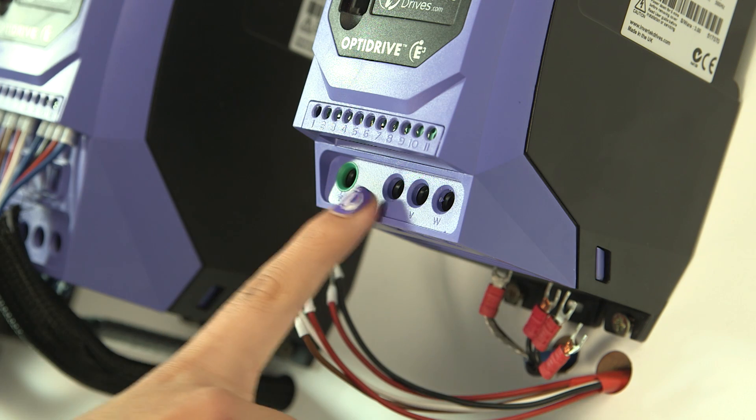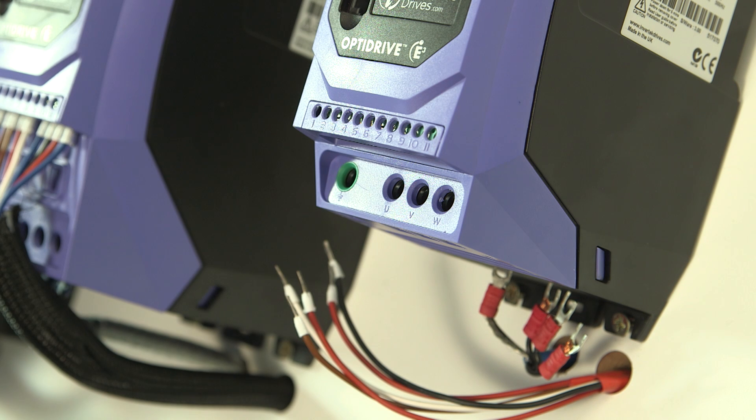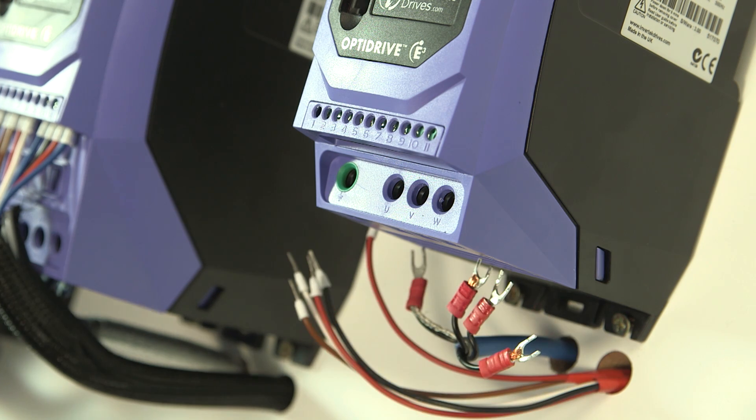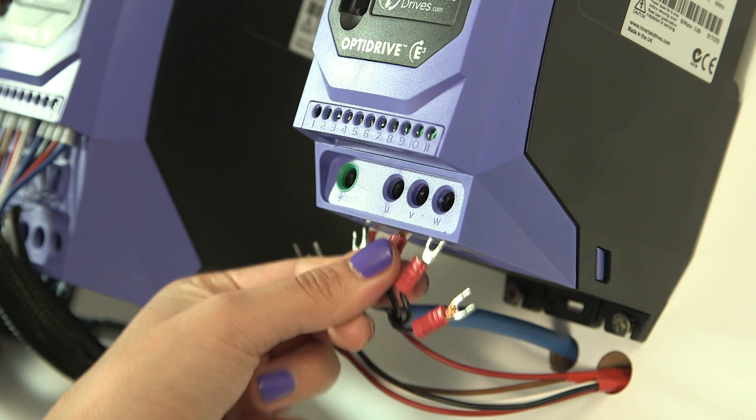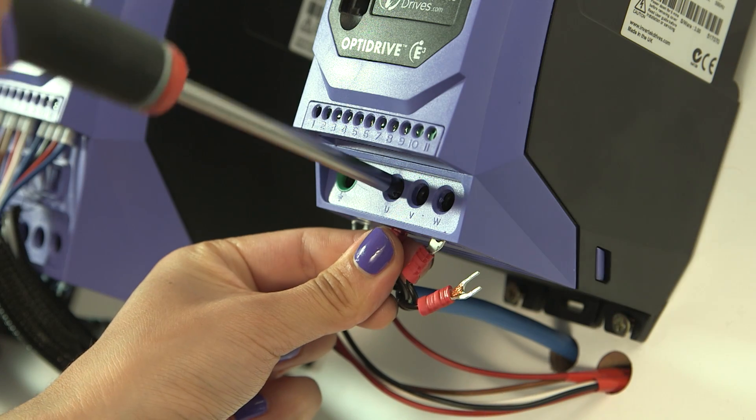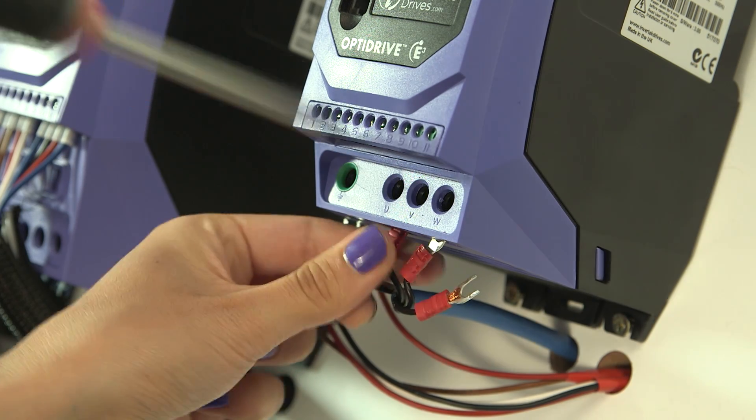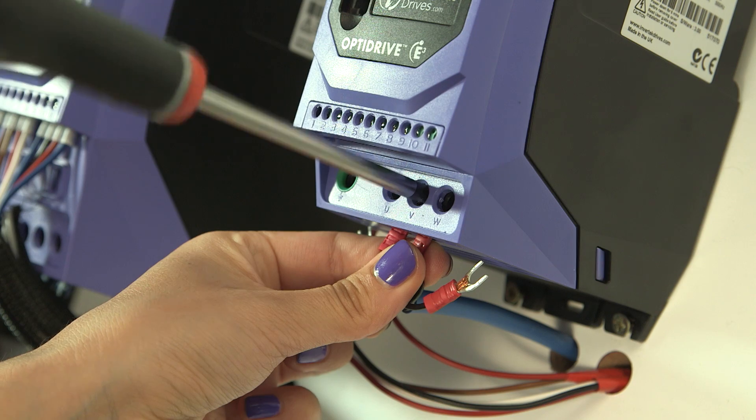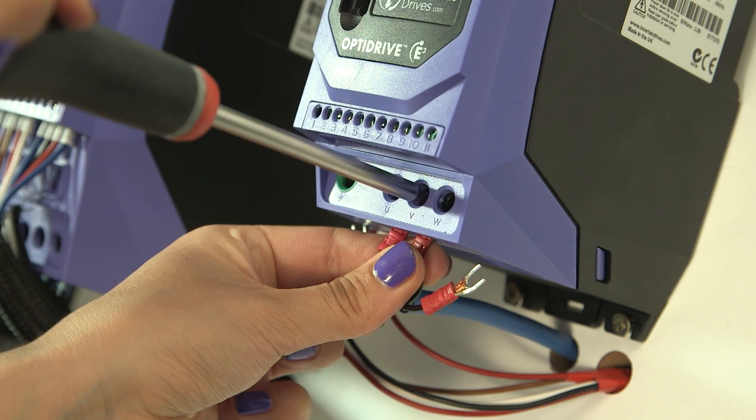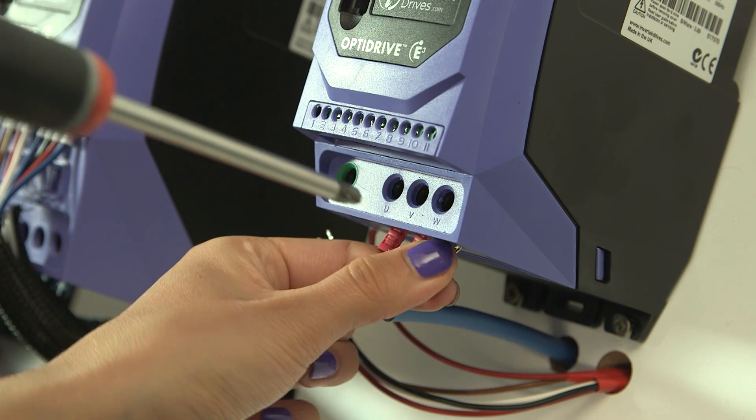Connect the motor to the E3 at the bottom. Many motors can be connected in star or delta for different supply voltages. Check the motor is correctly connected for the output voltage of the drive. In this case, the motor is delta connected for 230V three-phase operation. Connect U, V, and W to the corresponding motor terminals.